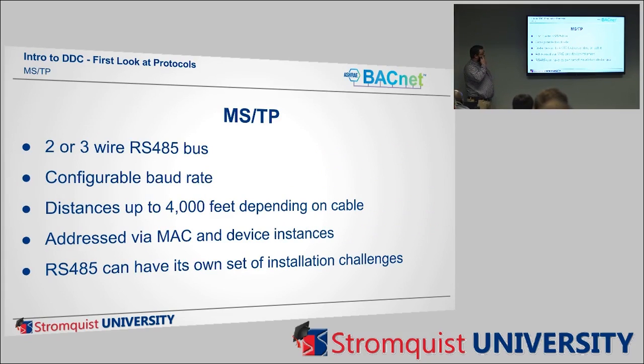All right, so MSTP can be a 2- or 3-wire bus. 3-wire bus is better. It's a lot more robust, and it's a lot easier to install as far as getting away with problems. The problem is it's more expensive. It's another wire, and it's more expensive to make a 3-wire bus controller. So most manufacturers, when you have a BACnet thermostat, it's just got 2 places to put wires. It doesn't have the reference. And that's just because money drives the industry and budgets. Not all manufacturers can afford to say, I'm just going to be 3-wire, which is better. Their controls will never be installed.